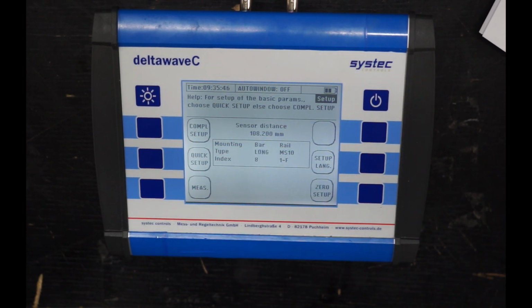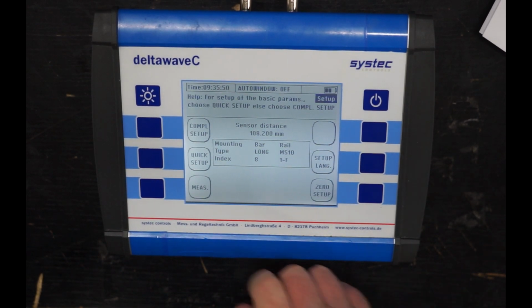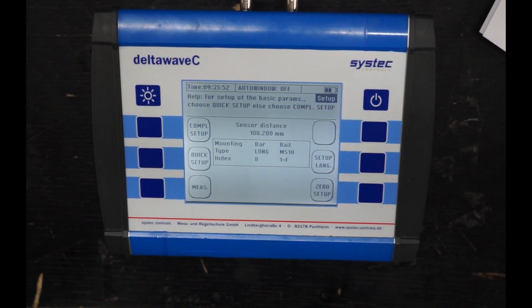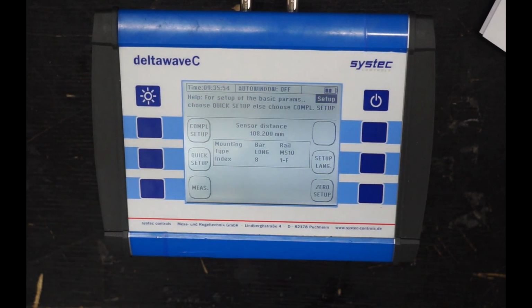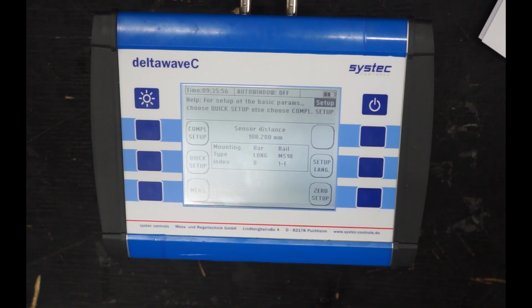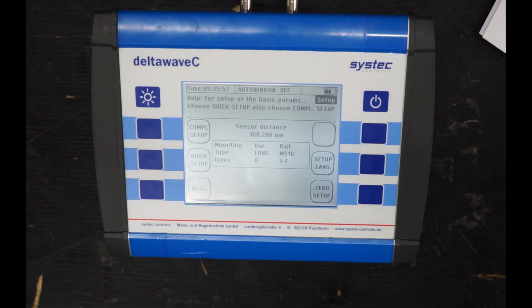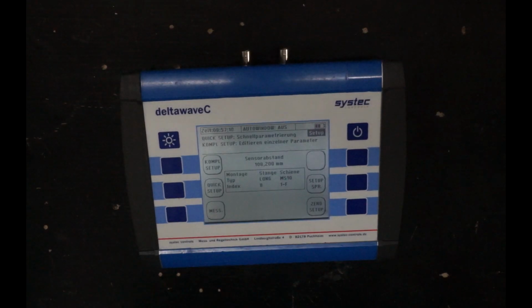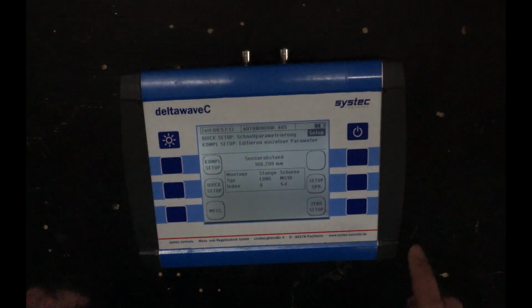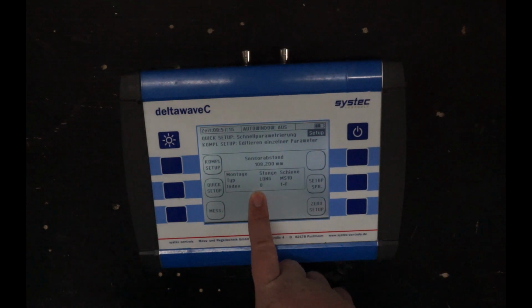In the final window, deltawaveC will show you the mounting distance of the transducers and also a number of index holes on our mounting rail. If possible, we always recommend using the mounting rail. When using the mounting rail correctly, it is very easy and safe to find the perfect distance between the 2 transducers. In this example, the distance is 8 holes on the mounting rail.